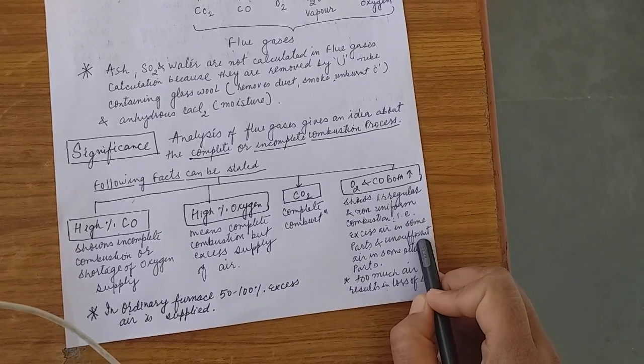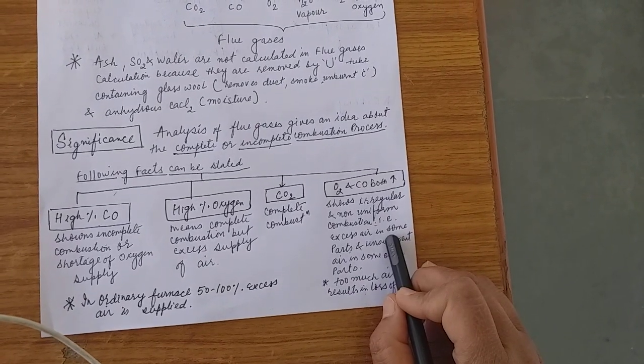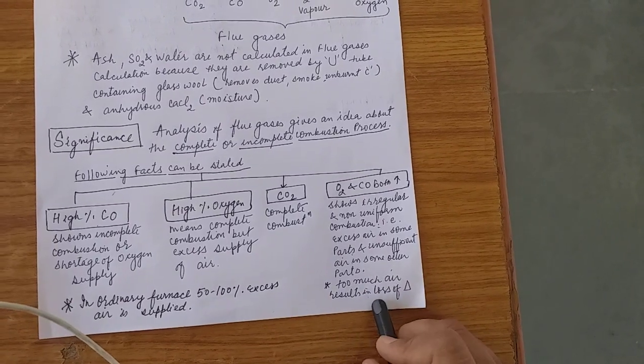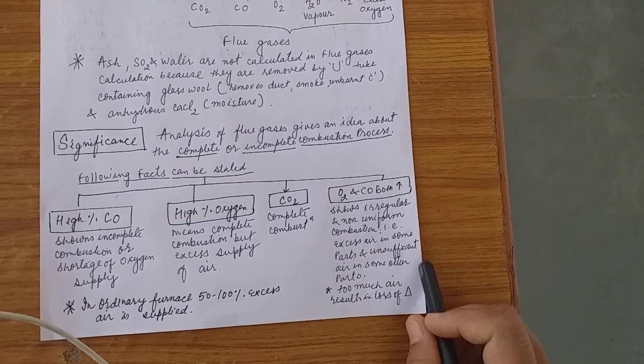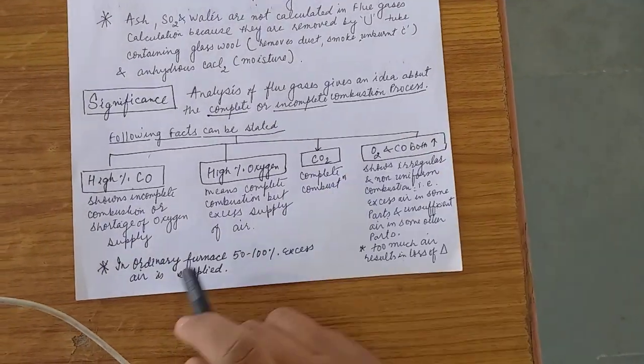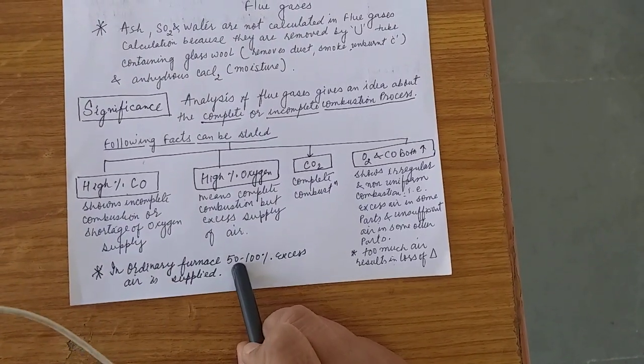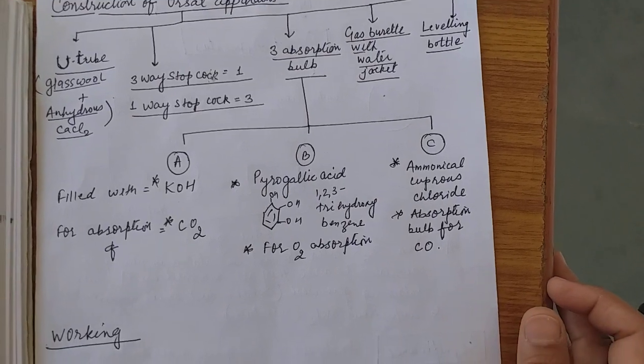That is some of the area with the excess of air and some of area with insufficient oxygen. Therefore, carbon monoxide is formed. Excess of air also results in loss of heat. Therefore, excess of air should be minimized. In ordinary furnace, 50 to 100 percent excess air is supplied.